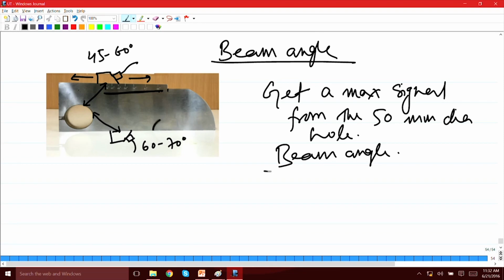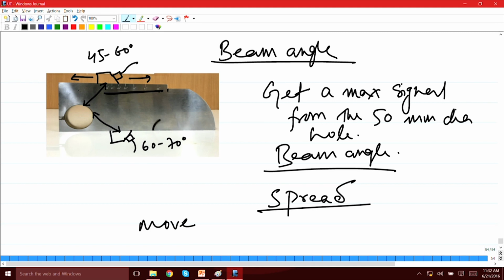But a beam angle will also have a spread, beam spread. Okay. So, this spread also you need to find out, as to how much is the spread in the angle. So, what you do, once you establish this angle and the corresponding point for the maximum signal, you move this probe again on both the sides from that point of maximum signal. So, first you move, for example, towards the left till the signal becomes 0.